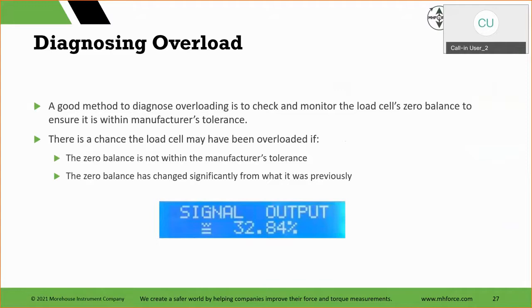You could have a load cell with a zero balance of 0.1% that shifted to maybe 0.5%. That tells you someone probably applied 155%, 160%, real easy. And then if your output shifted, what do you do? Well, as long as they don't continue to overload it and it's still within the manufacturer's tolerance, you're just going to have that shift, a bump in the data. More than likely, you should shorten your recalibration interval. If you're on a year and you had a bump, maybe you shorten it to 6 months, maybe to 3/4 of a year. Whatever gives you peace of mind to say, okay, we're good. I know that someone did this. As long as we continue to monitor it, we're good. So just some additional tricks there.